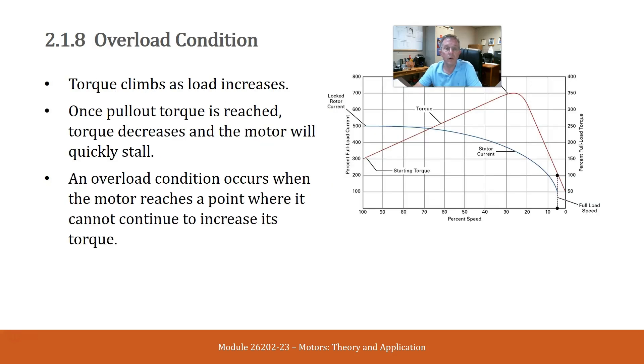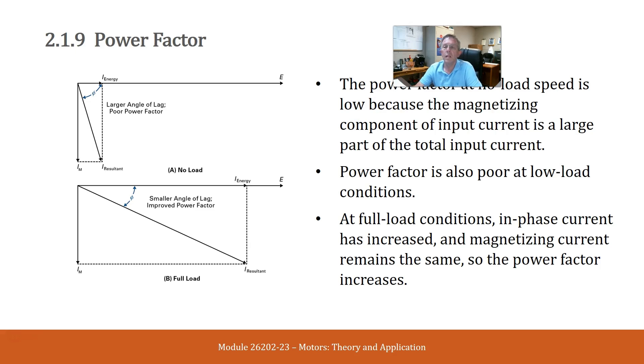Torque climbs as load increases. Once pull-out torque is reached, torque decreases and the motor will quickly stall. An overload condition occurs when the motor reaches a point where it cannot continue to increase its torque. The power factor at no load speed is low because the magnetizing component of input current is a large part of the total input current. Power factor is also poor at light load condition. At full load conditions, in-phase current has increased and magnetizing current remains the same, so the power factor increases.